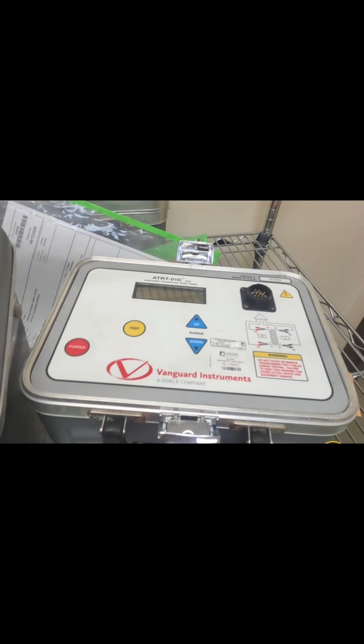So here's why this test is non-negotiable for substation techs. First, it catches internal damage. If a lightning strike on the grid or a short circuit forces the coils to shift or burn through the insulation, this tester flags it instantly before the whole thing becomes a catastrophic failure.